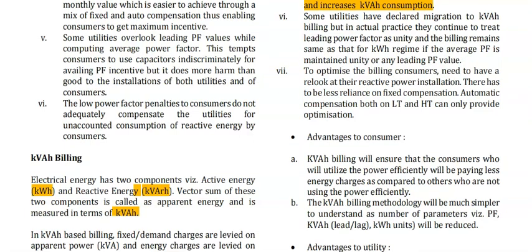And the sixth point is that some utilities have declared migration to kVAh billing, but in actual practice they continue to treat leading power factor as unity, and the billing remains the same as the kilowatt hour regime if the average power factor is maintained at unity or any leading power factor. Some utilities, some boards, are generally doing this. To optimize the billing, the consumer needs to take a relook at their reactive power installation. There has to be less reliance on fixed compensation. Automatic compensation, both LT and HT, can be provided for optimization.